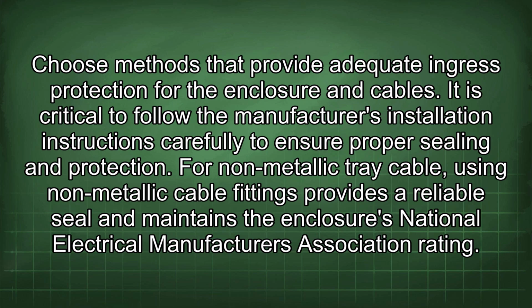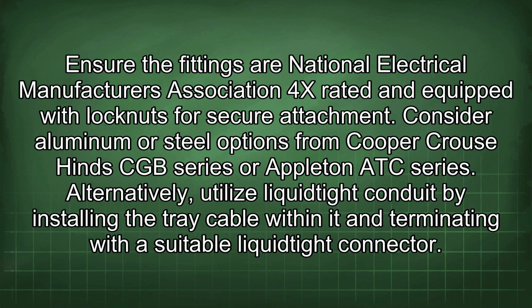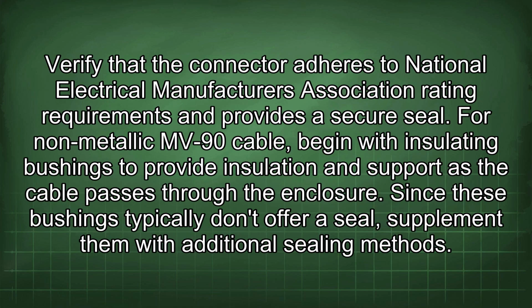For non-metallic tray cable, using non-metallic cable fittings provides a reliable seal and maintains the enclosure's National Electrical Manufacturers Association rating. Ensure the fittings are National Electrical Manufacturers Association 4X rated and equipped with lock nuts for secure attachment. Consider aluminum or steel options from Cooper Crouse-Hinds CGB series or Appleton ATC series. Alternatively, utilize liquid-tight conduit by installing the tray cable within it and terminating with a suitable liquid-tight connector. Verify that the connector adheres to National Electrical Manufacturers Association rating requirements and provides a secure seal.